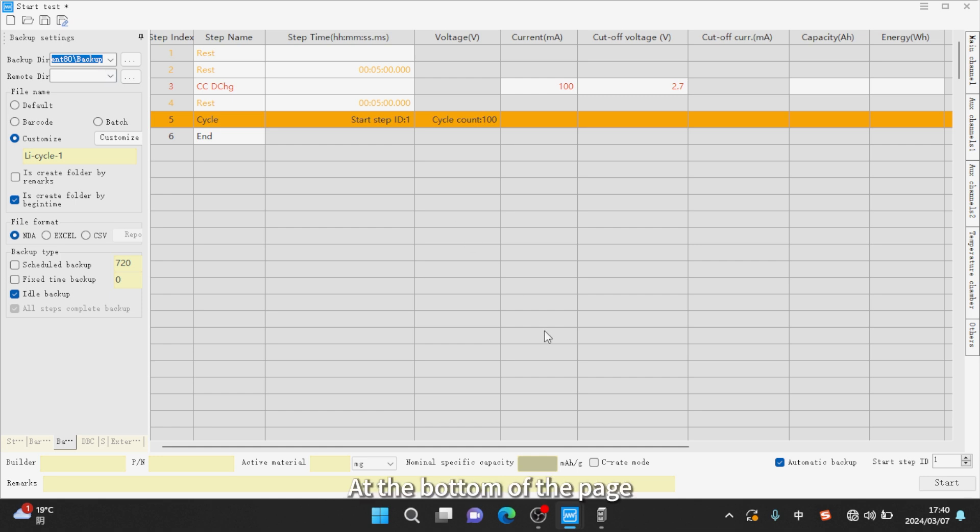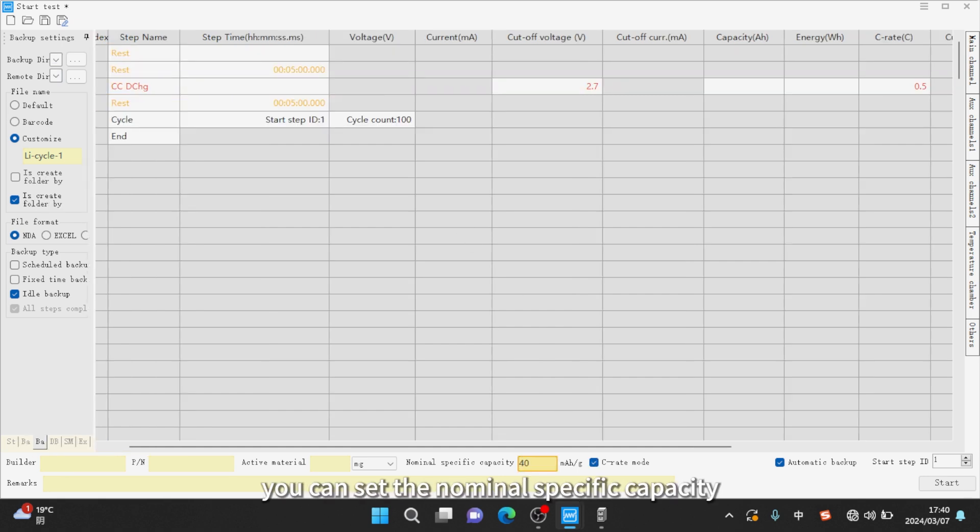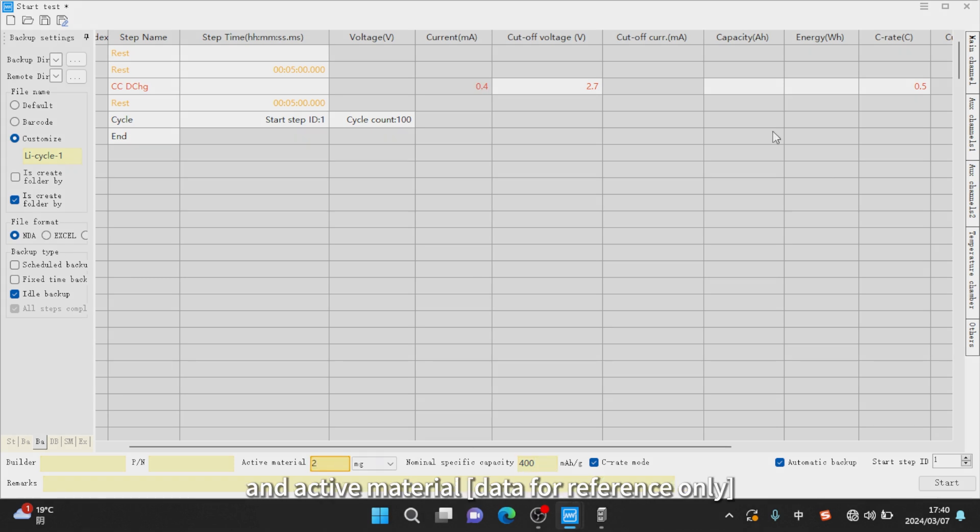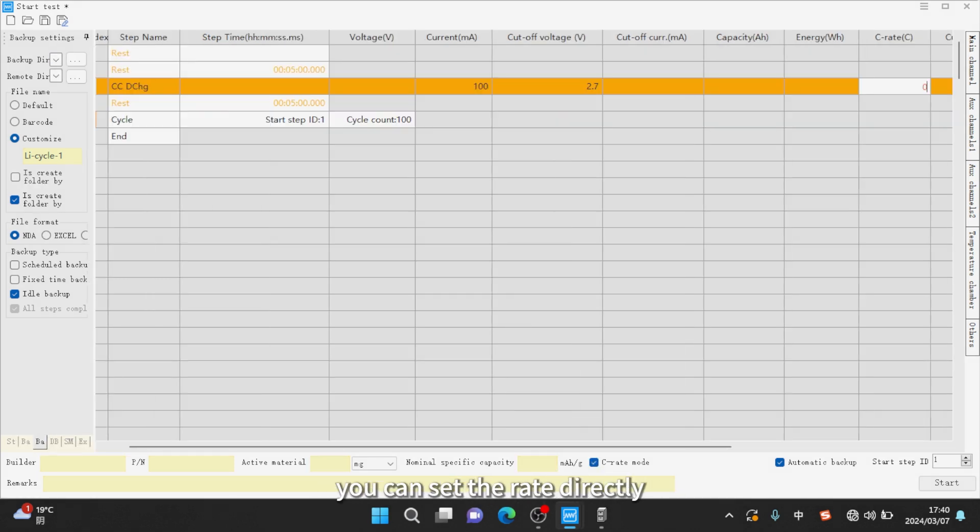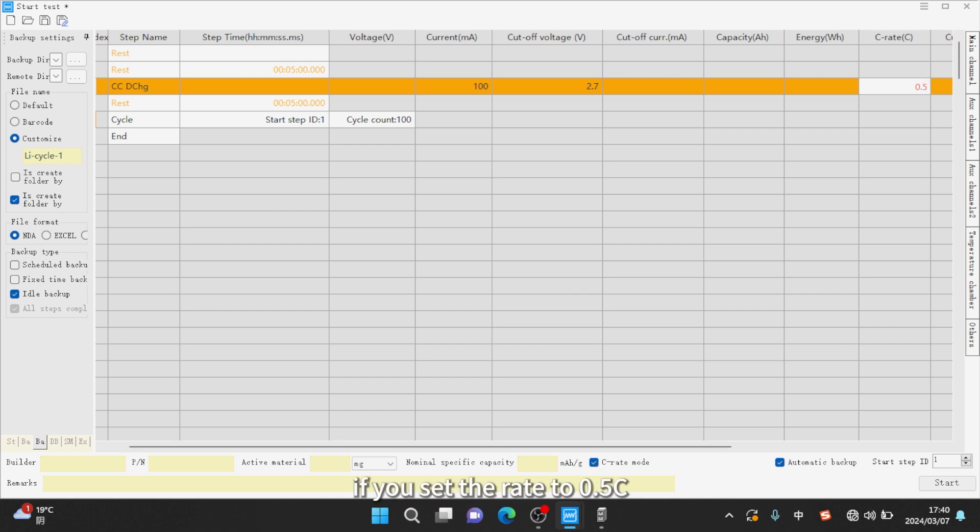At the bottom of the page, you can set the nominal specific capacity and active material. After checking the C-Rate mode, you can set the rate directly. For example, if you set the rate to 0.5C...